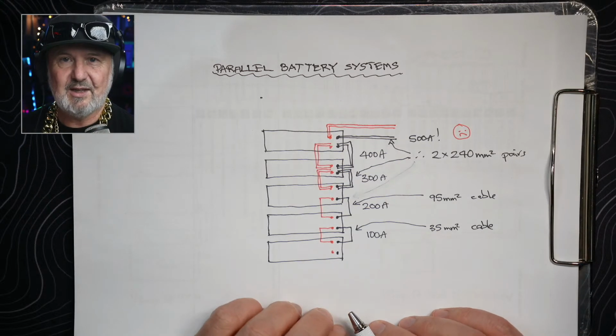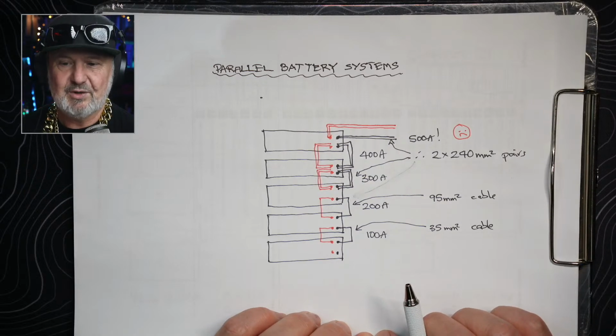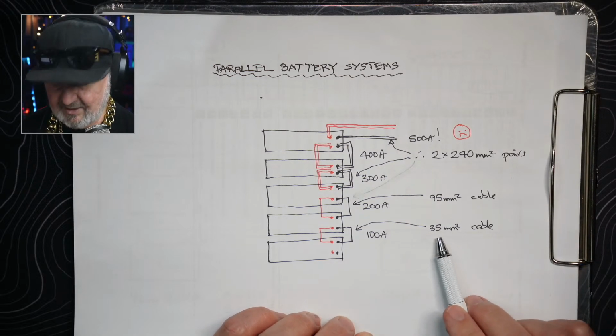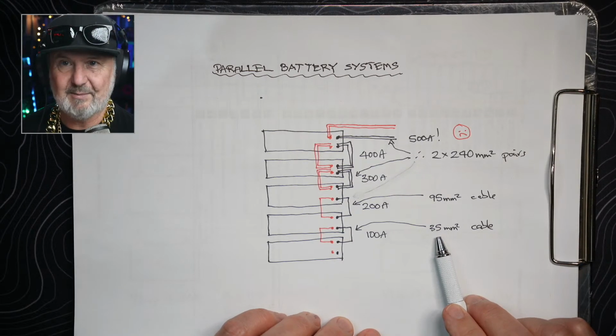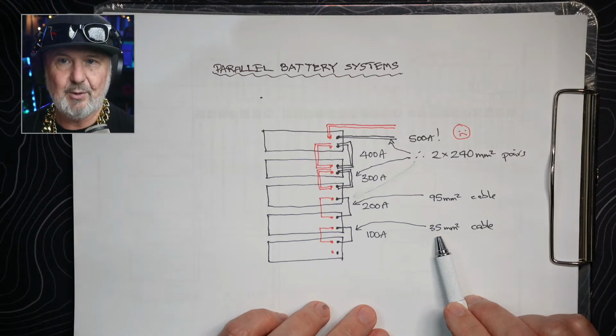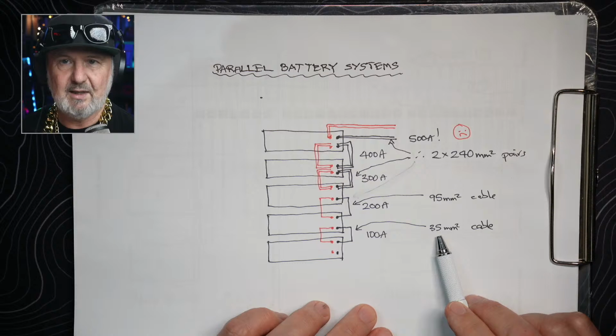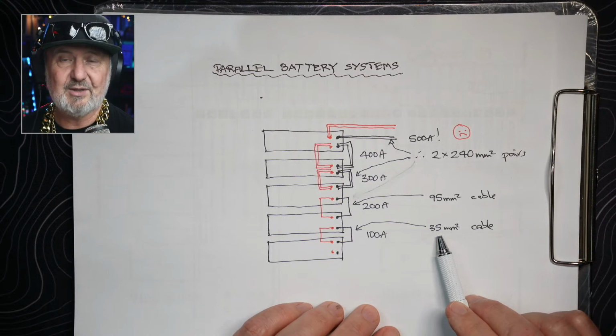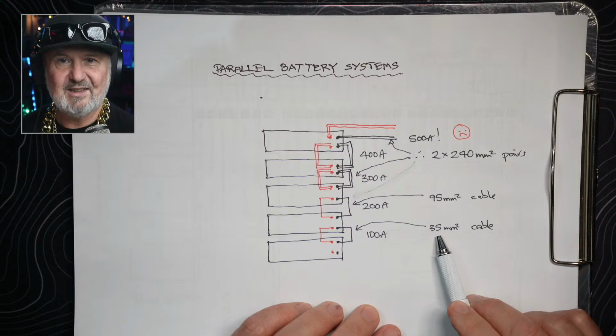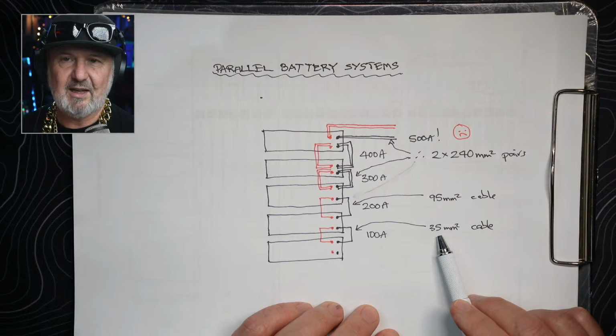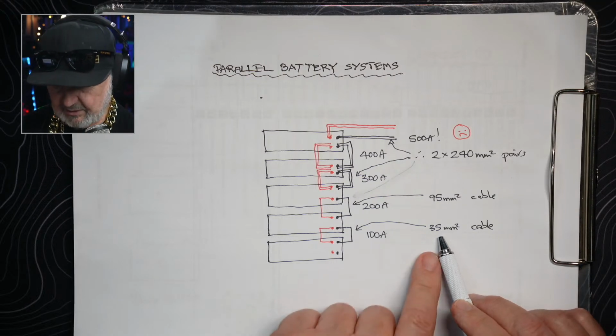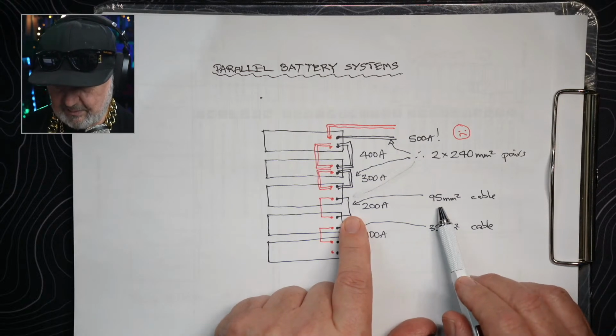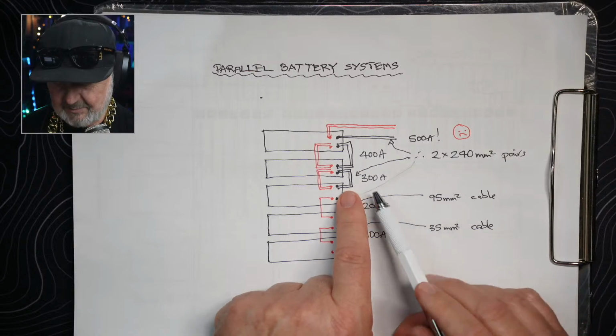And what do you know? The ones supplied with the units are little bits of 35mm cable with some quick connectors on them. So really the only one that was rated correctly was the first one for 100 amps. If I look at the tables in 3008, which you can use for DC sizing as well, even it says so in the preface. By the way, we're updating 3008 to have some specific DC tables. There's always less loss in a DC cable compared to AC. You don't have skin effect or proximity effect. So if you can meet the requirements for AC current, you'll easily be fine for DC. So 35mm cable would be adequate here, but really we need to step up to 95mm cable for the next battery. Then we get up to 300 amps.